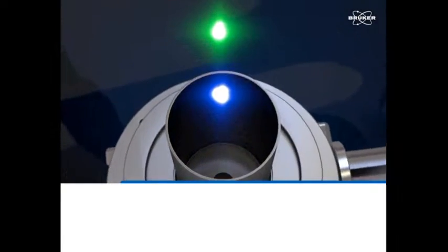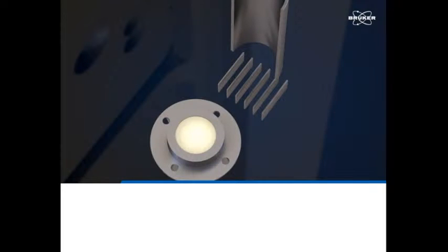In this process, precursor ions and their respective fragments travel together at the same speed. Based on the expected time of flight of the precursor ions, specific ion packages may be individually selected, and all other ions blocked from continuing through the flight tube. The selected ions are then re-accelerated, with the precursor and fragment ions traveling at different speeds towards the reflector detector. The ions travel via the reflector towards the detector, and thus a TOF/TOF spectrum is recorded.